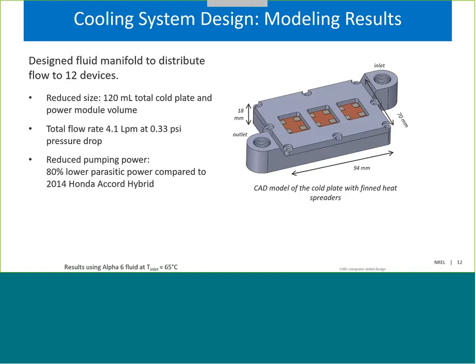And so the total volume for this conceptual power module and cold plate is 120 milliliters, and that's half of the 240 milliliters that we estimate is needed to achieve a power density of 100 kilowatts per liter. And so we're meeting the volume requirements. The total flow rate requirement is 4.1 liters per minute, and the computed pressure drop from the inlet to the outlet is about 0.3 psi.